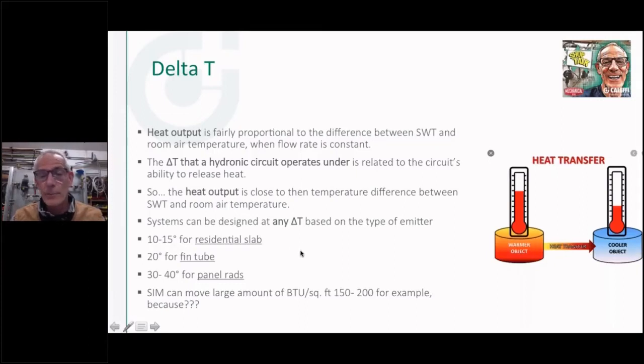We've used this number 20 for years. I don't know where it came from. It just makes the math easy. Maybe that was the simplest thing. But it doesn't have to be that, and the system doesn't have to stay at that 20-degree delta T. From the turn on to the turn off point, it can vary a little bit, and as the load changes against that heat emitter, the delta T will always move.